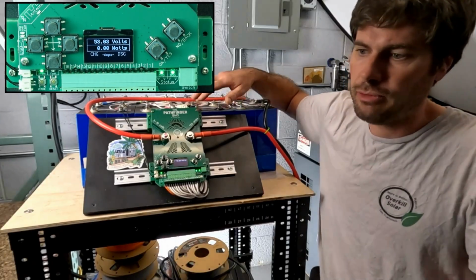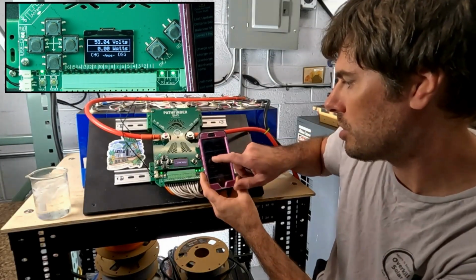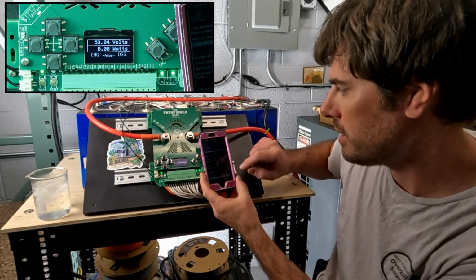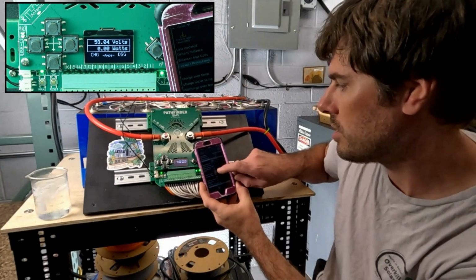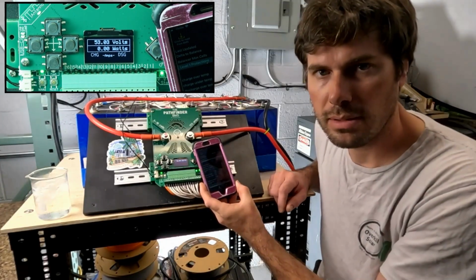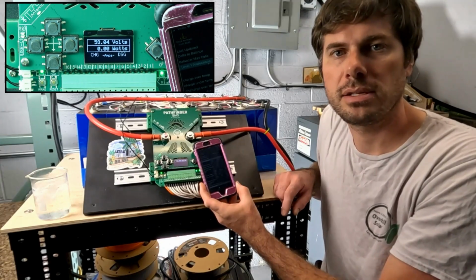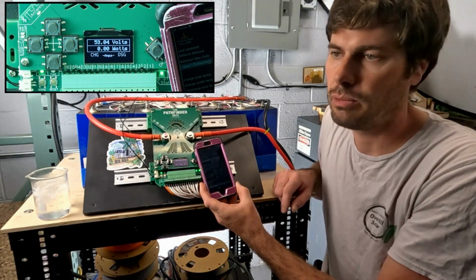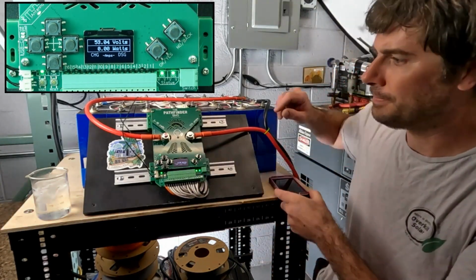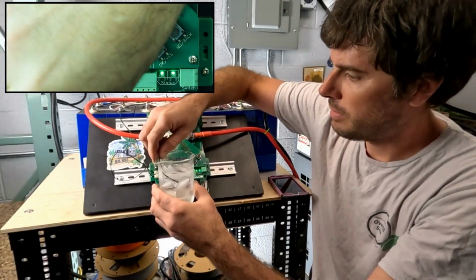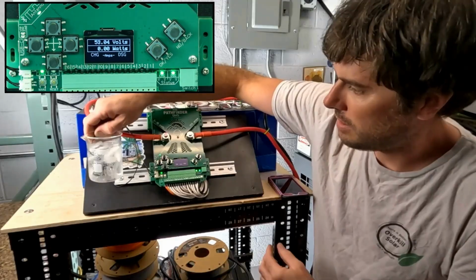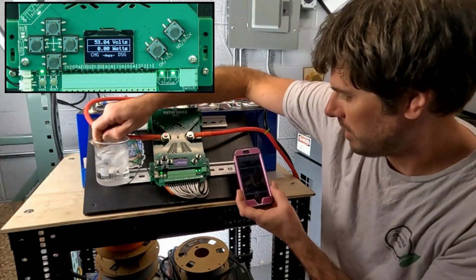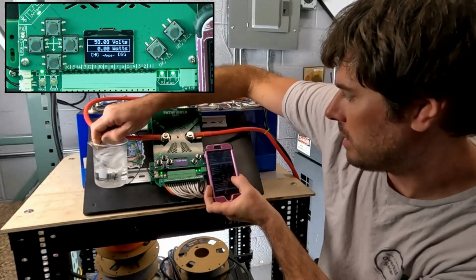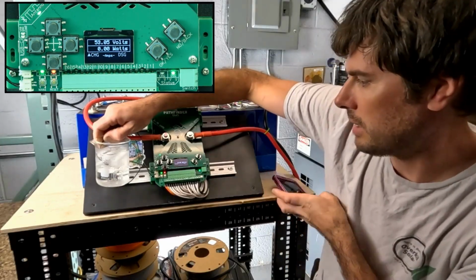lithium iron phosphate. By default, charge under temperature is set to 0 degrees Celsius, and discharge under temp is set to -20 degrees Celsius. So we'll only be able to test the charge under temperature protection with ice water. So let's go ahead and do that now. When we dip probe number 1 in the ice water, we should see the charge LED turn off after delay, which is set to 2 seconds.